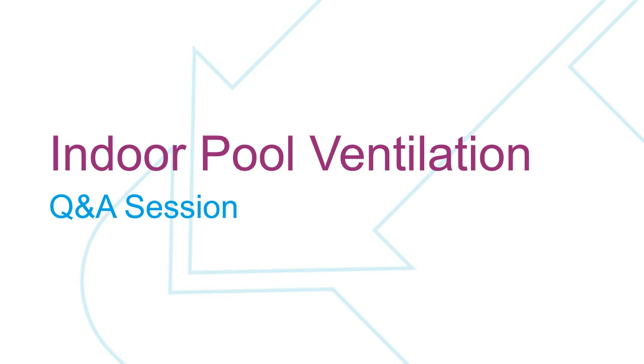Do you suggest reducing outside air to the minimum during summer and then just use the maximum 50% during winter? No, it's actually the flip side of that. And people ask that question with good reason. So in winter, you're going to run the lowest you can for indoor air quality because otherwise you'll dry the space out too much.